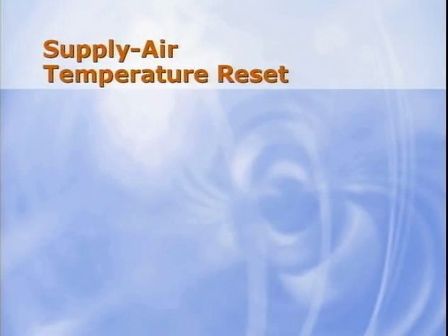Next topic, supply air temperature reset. It's tempting to raise the supply air temperature at part load conditions in an attempt to save compressor or reheat energy. There are applications where the temptation is worth the reward. However, this practice should not be used indiscriminately. Let's take a look at the effects of supply air temperature reset.